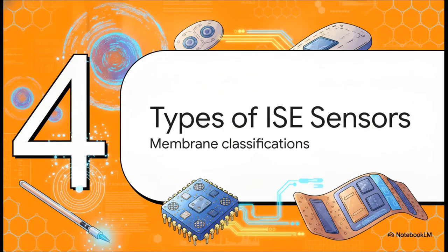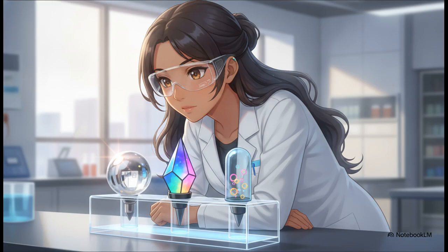Which brings us to section 4, types of ISE sensors. There's basically a quick mental checklist of the three main membrane categories. First, glass membranes, like your ubiquitous pH electrode made of silicate glass. Second, solid-state membranes. These use highly insoluble crystals, like using a lanthanum fluoride crystal to detect fluoride. And finally, polymer membranes. These rely on flexible plastics like PVC mixed with liquid plasticizers, and of course, those incredible ionophores we were just talking about.